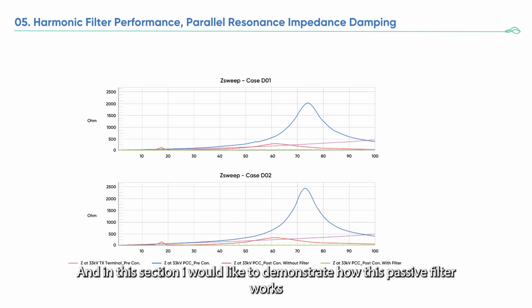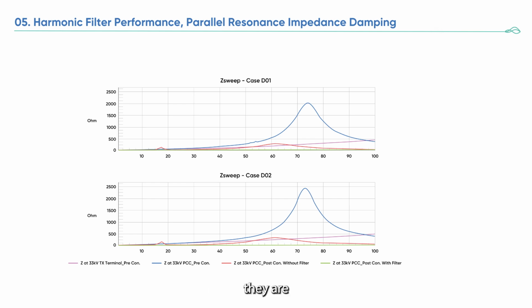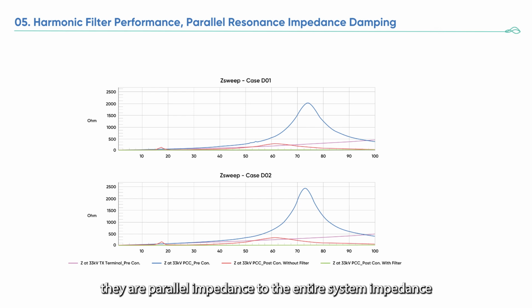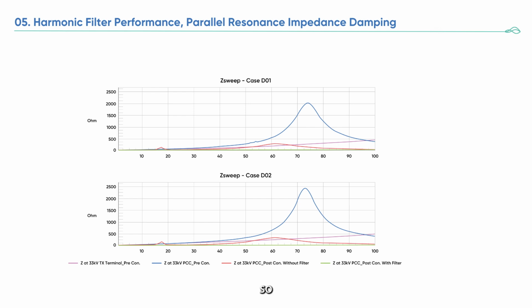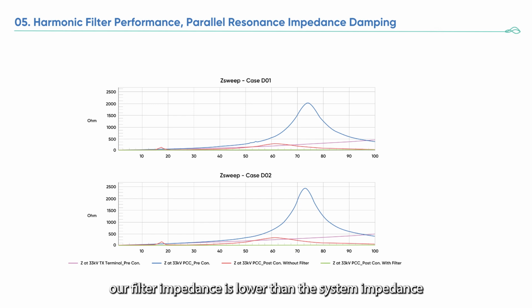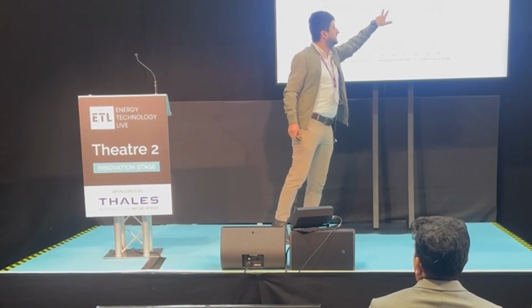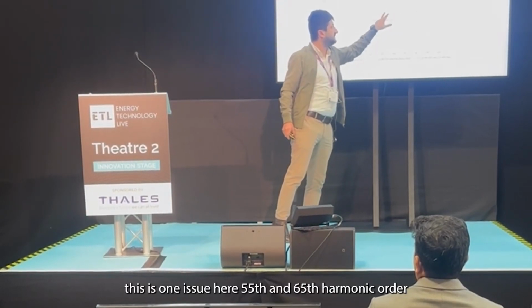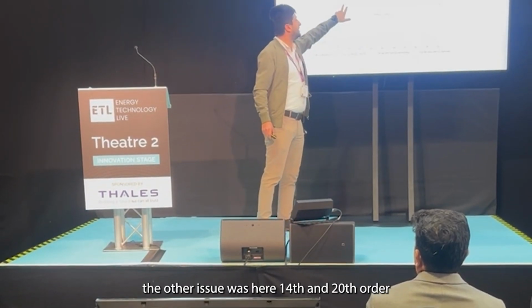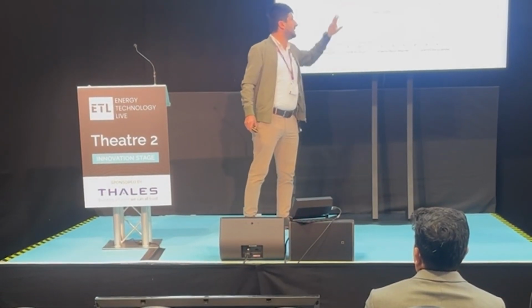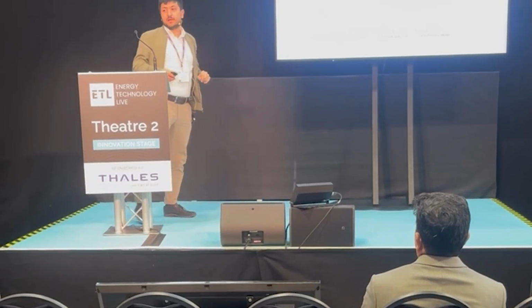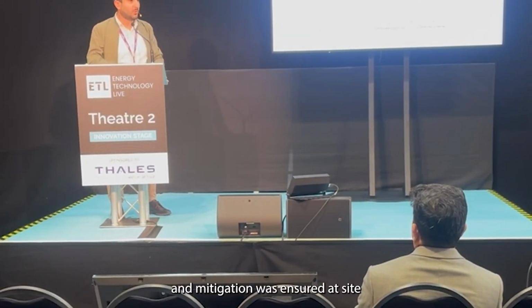And in this section, I would like to demonstrate how this passive filter works. Mainly, passive filters are a parallel resonance to the entire system. They are parallel impedance to the entire system impedance. So our filter impedance is lower than the system impedance, and we are trying to dampen network impedance. If you can see here, this is one issue here, 55th and 65th harmonic order. The other issue was here, 14th and 20th order. These two resonances were damped, and mitigation was ensured at site.